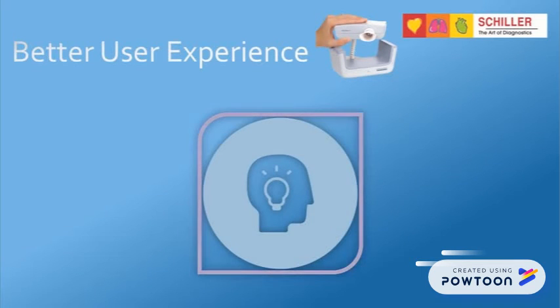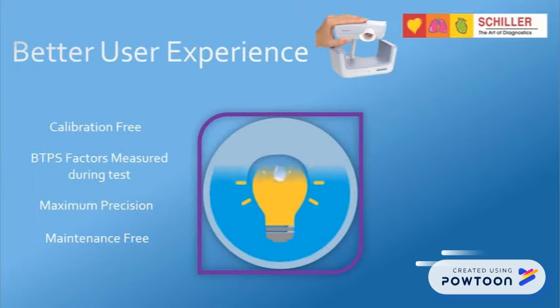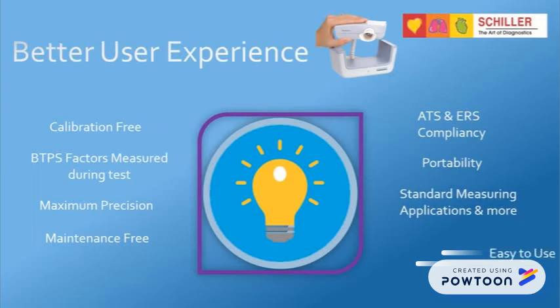Spirometer's ultrasonic technology eliminates the need for calibration, saving time and allowing more tests to be performed. Body temperature and pressure sensors are measured during each test for maximum precision. The Spirometer fully conforms to ATS and ERS standards. It is portable, so you can perform tests in your office or on the field. Just change the mouthpiece and get started.